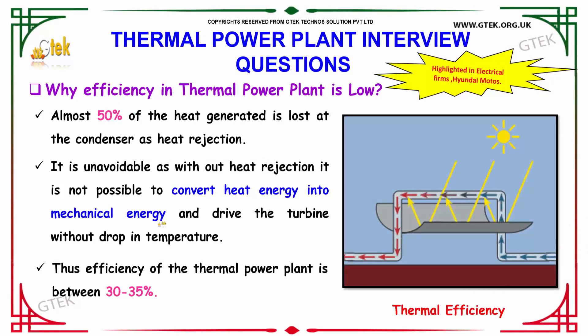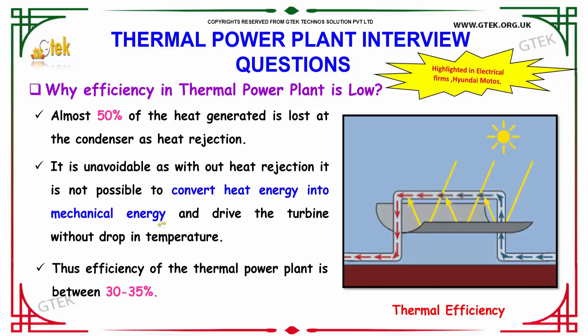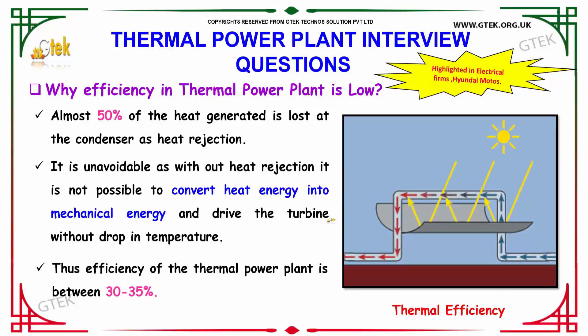Why is the efficiency in a thermal power plant low? Almost 50% of the heat generated is lost at the condenser as heat rejection. It is unavoidable because without heat rejection it is not possible to convert heat energy into mechanical energy that drives the turbine without a drop in temperature. Thus, the efficiency of the thermal power plant is between 30 to 35%.